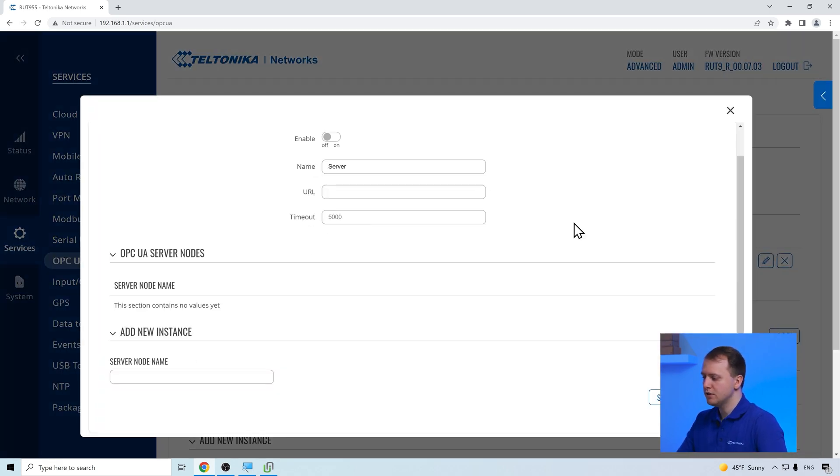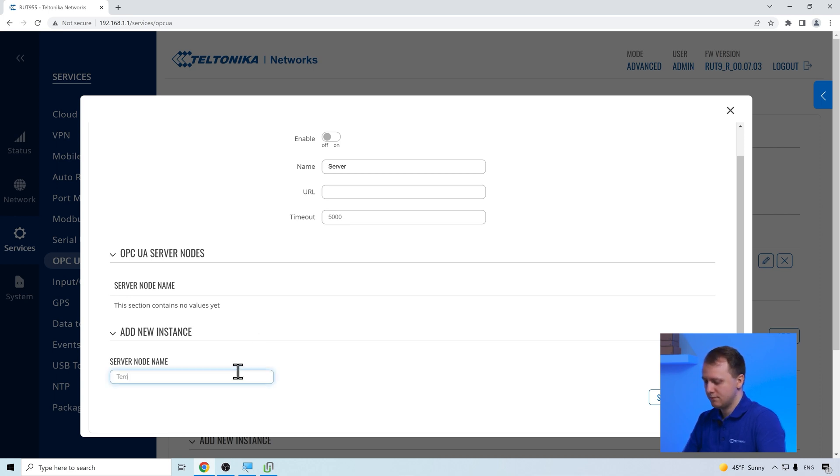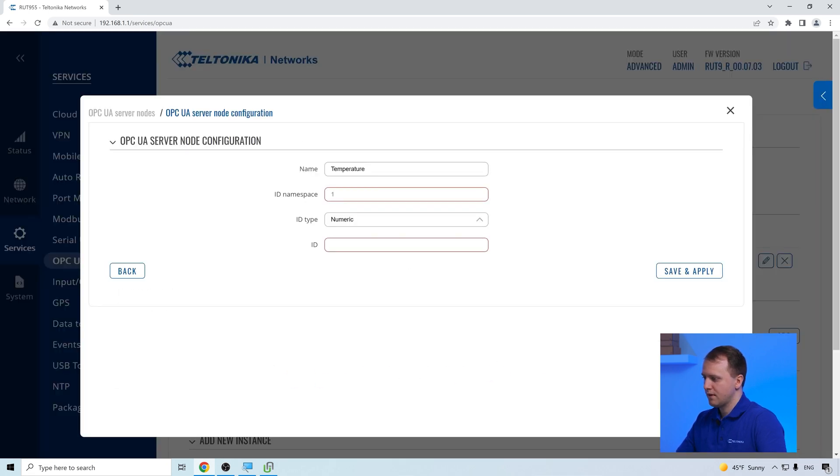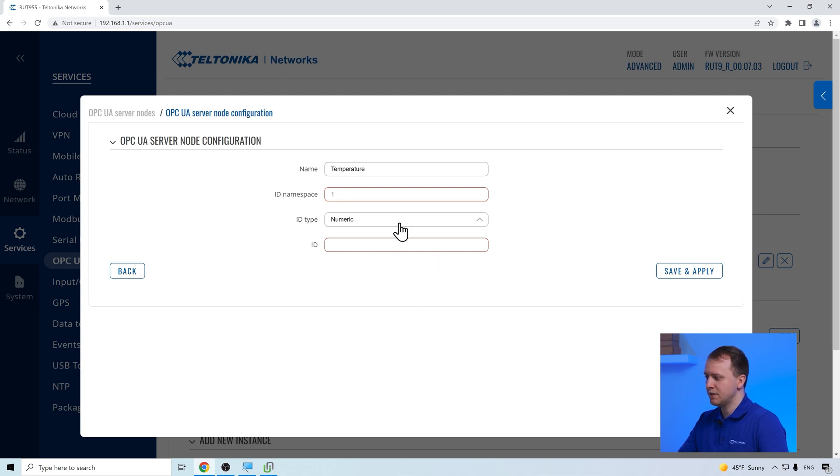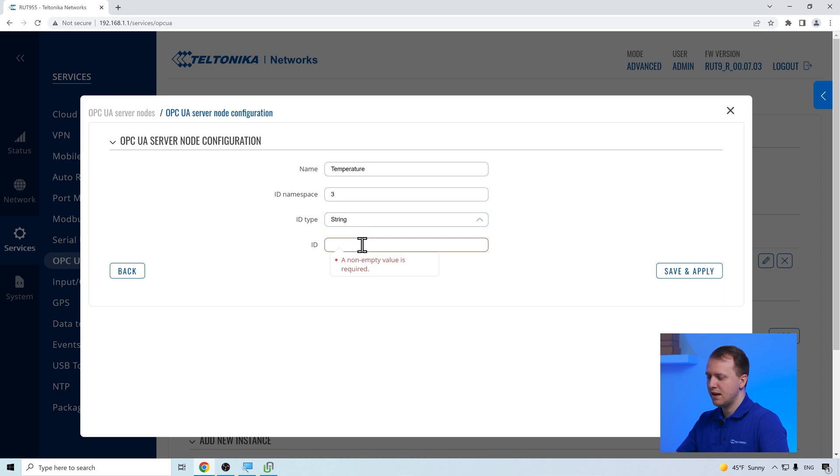In the server configuration page, we add the server nodes that extract specific information from the server. In our example, we choose to gather air humidity and air temperature values. When adding a node, we have to insert the namespace index, the ID type and the ID itself.